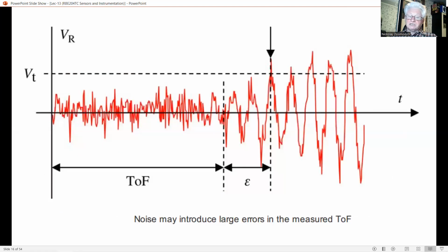The most common detection method for the echo burst is a threshold applied to the receiver signal. The TOF is set by the first time the echo exceeds the threshold. The threshold must be well above the noise level to prevent noise being interpreted as the incoming echo. On the other hand, when the threshold is too high, one or more periods of the received signal can be missed, as shown in this video.